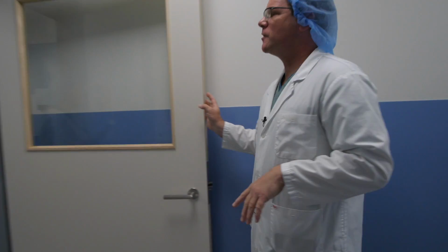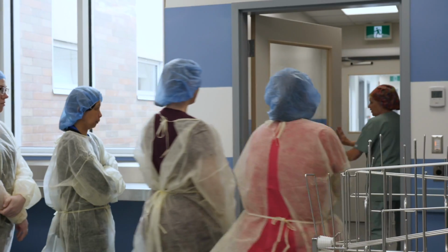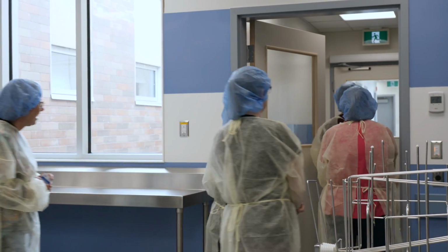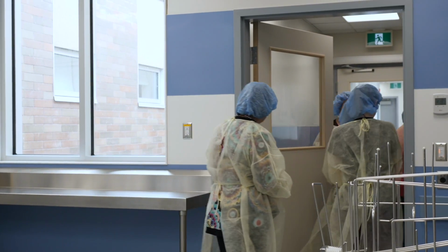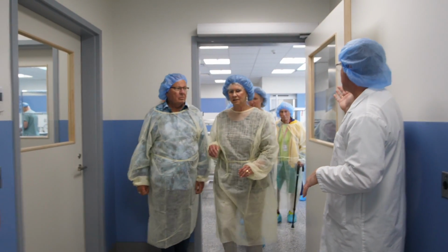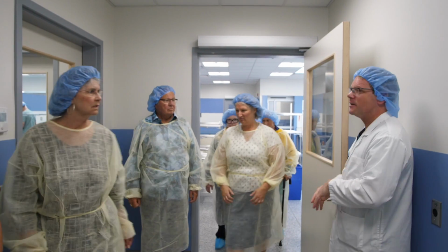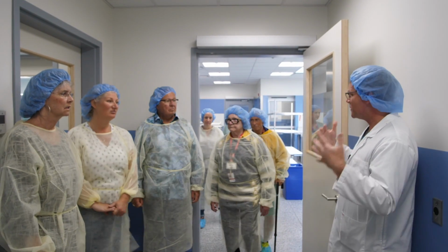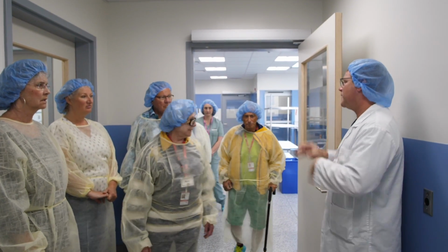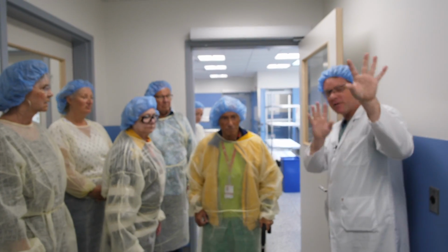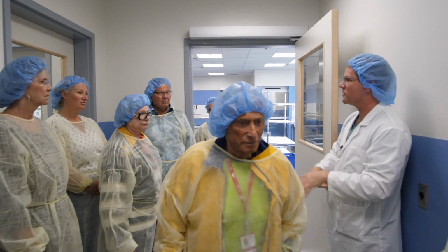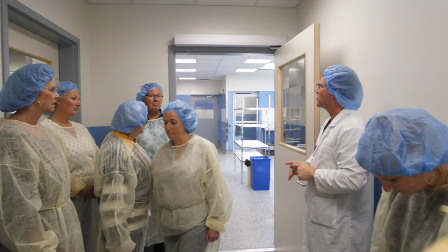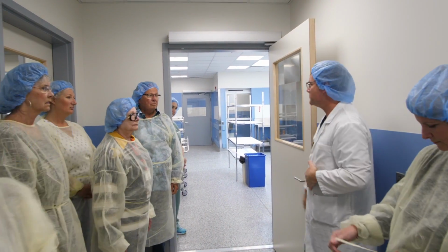So with every MDRD, we have to create an ante-room or an area of protection for both our staff and for the risk for contamination elsewhere. We have 2 ante-rooms in the front, one for carts and one for our nurses. This is a secondary ante-room that we have to separate our decontaminated area with our clean area, as well as with our endoscopy area. So this is kind of an area where we can prevent any cross-contamination.